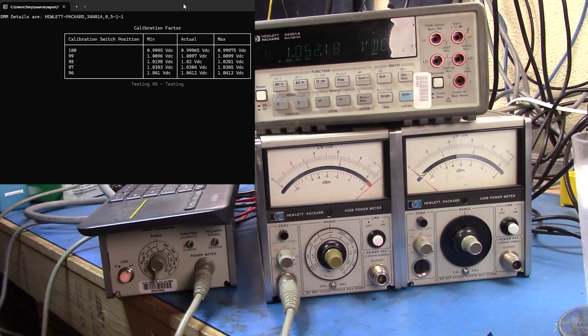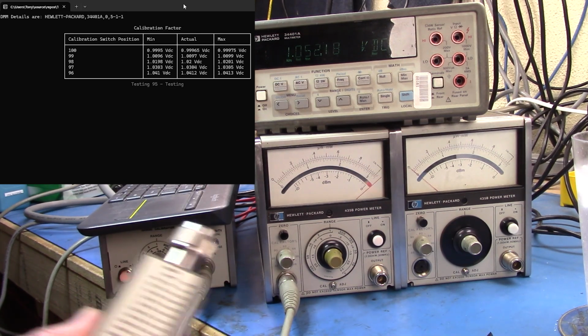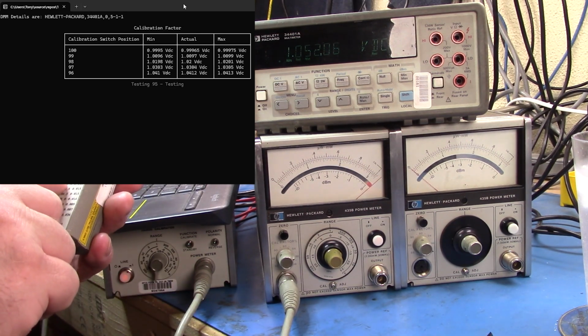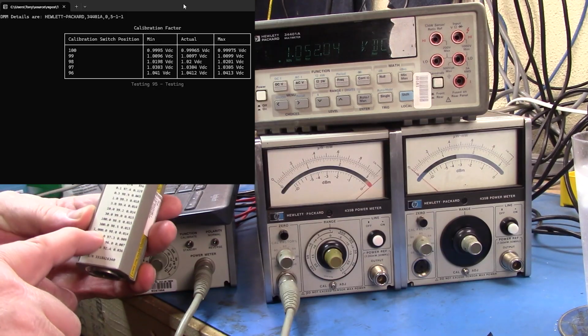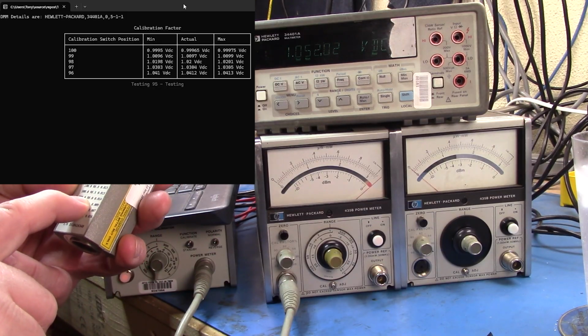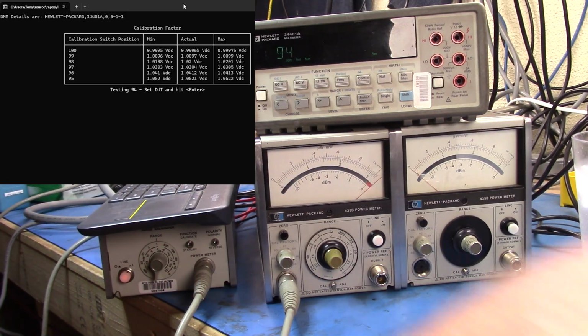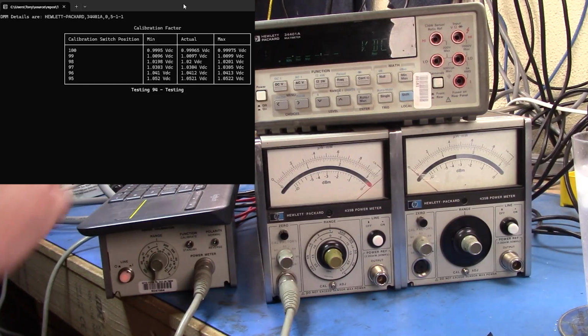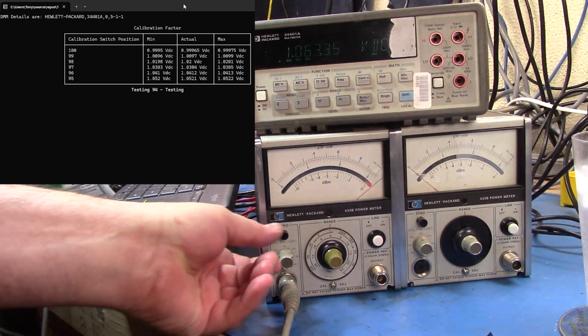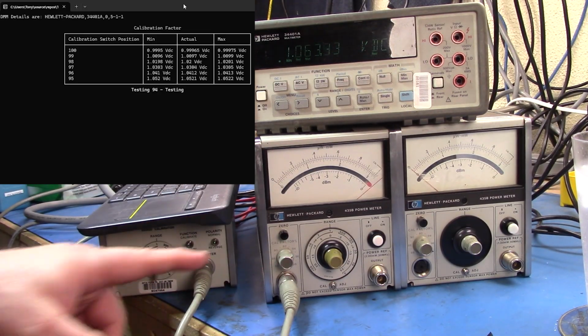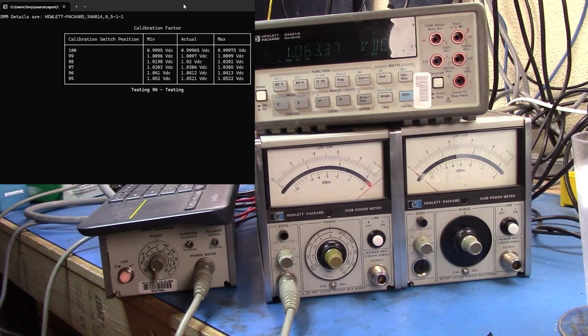How you would use it is, for example, if we were measuring a 1 gigahertz signal and we wanted to check the power on this, what I would do is I would go to my sensor, I would look down to where it said 1 gigahertz. In this particular case, it says 98% calibration factor. And so then I would dial in 98% on this knob here and take my measurement.